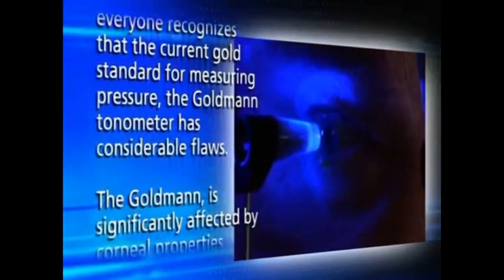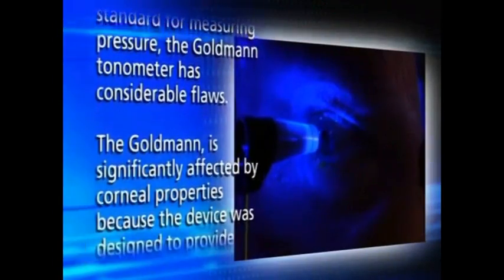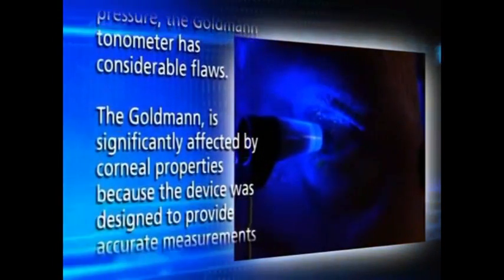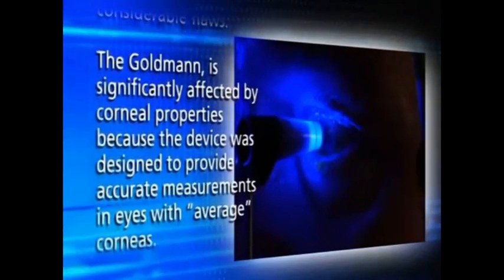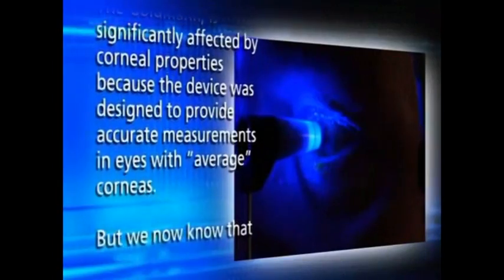By now, nearly everyone recognizes that the current gold standard for measuring pressure, the Goldmann tonometer, has considerable flaws. The Goldmann is significantly affected by corneal properties because the device was designed to provide accurate measurements in eyes with average corneas.